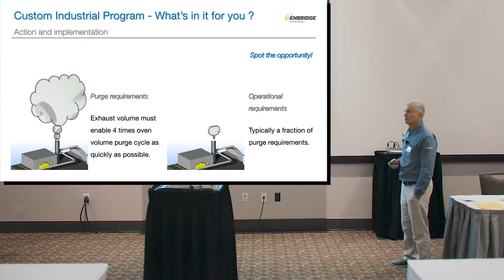Third case, spot opportunity. Remember the purge requirements and how operation requires a fraction. And most people who don't have direct experience with these ovens will say, big deal. Well, the problem is, for a typical gas-fired convection oven, if you put 100 units of energy in, these are the losses, you will get 22 units of 100 units of energy actually into the product. So remember how we talked about heat to load that you actually need? 22% of your overall heat you paid for.